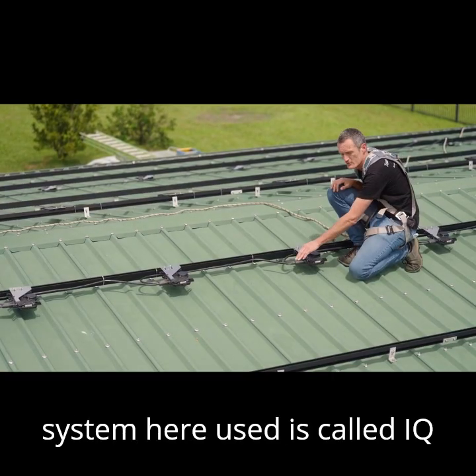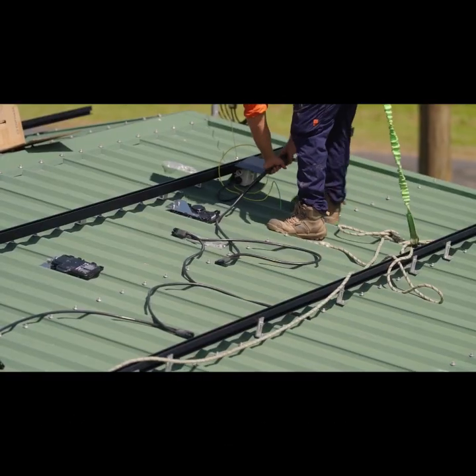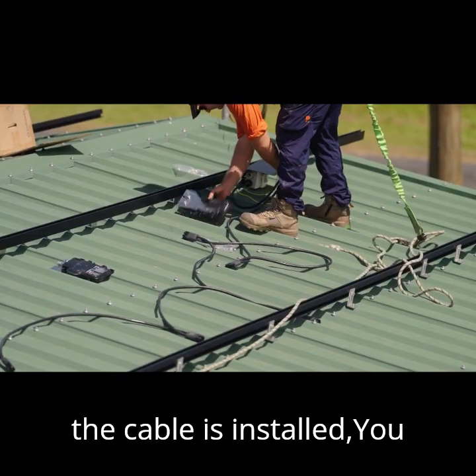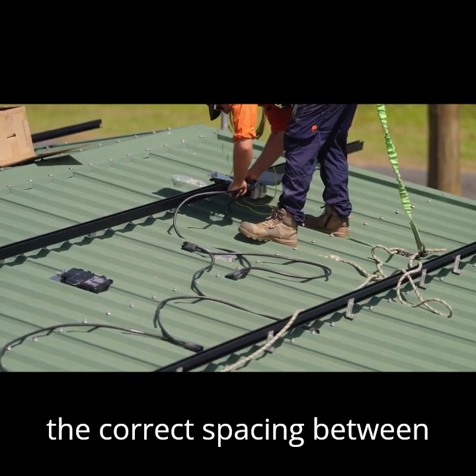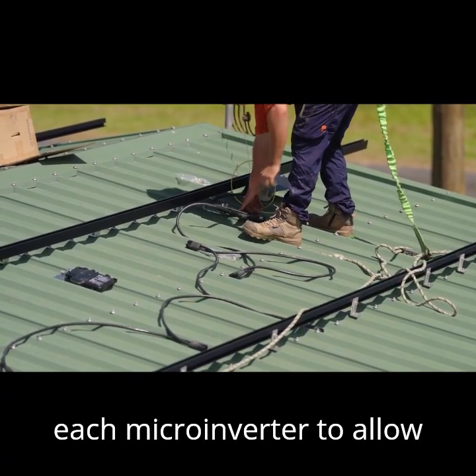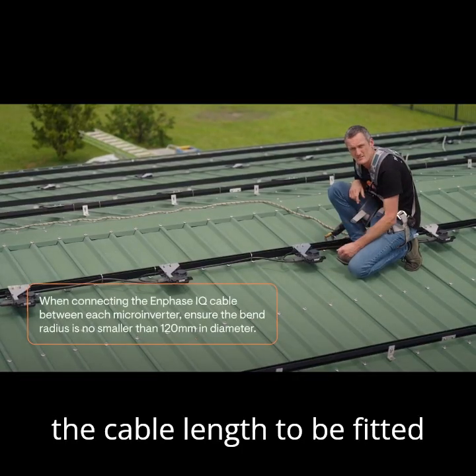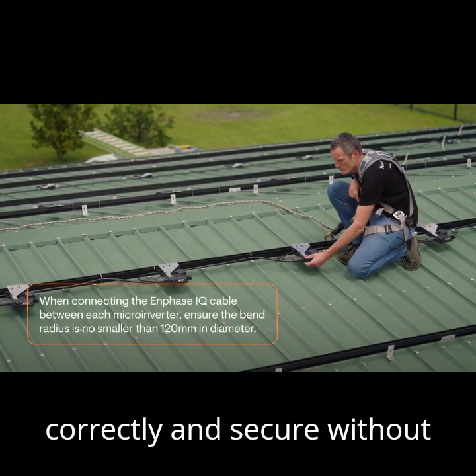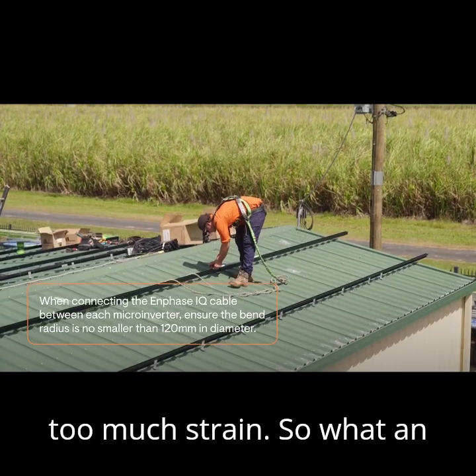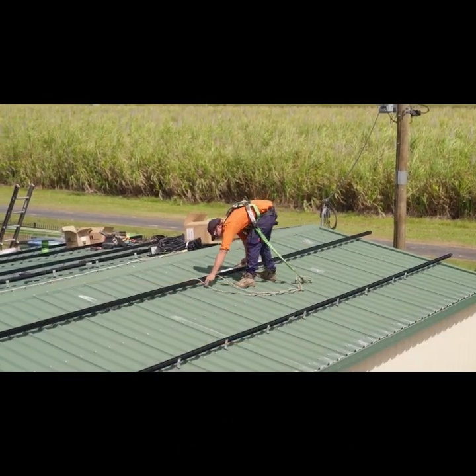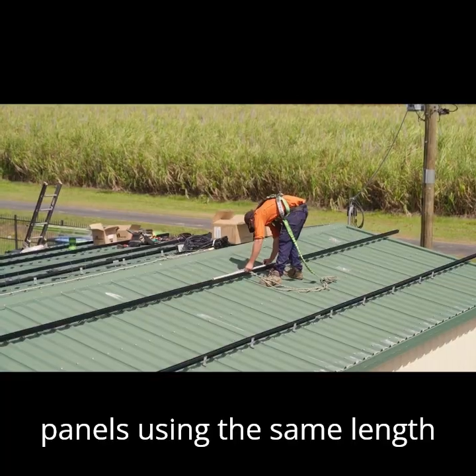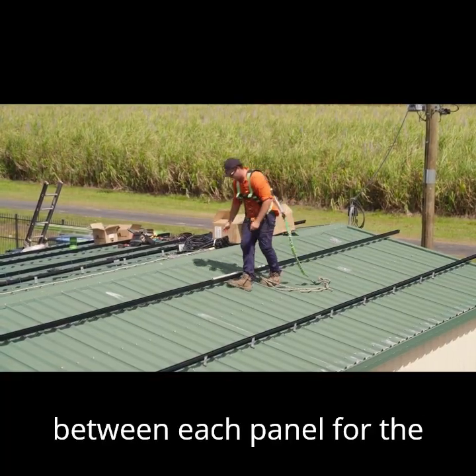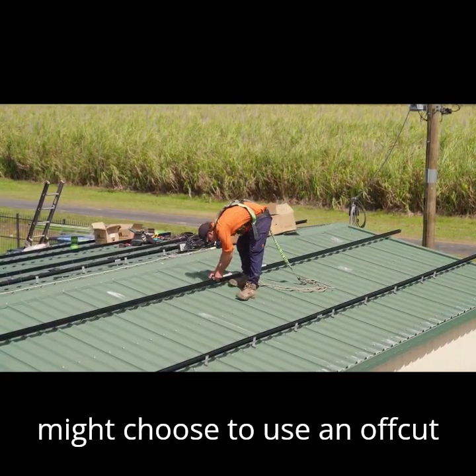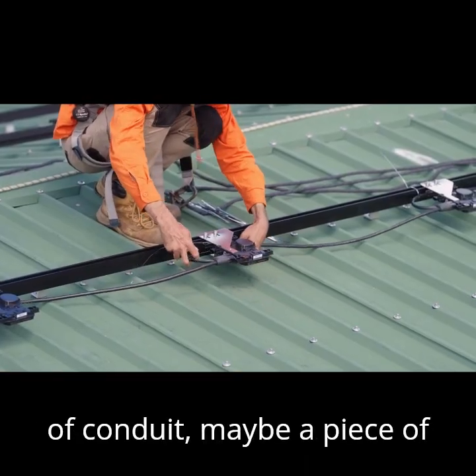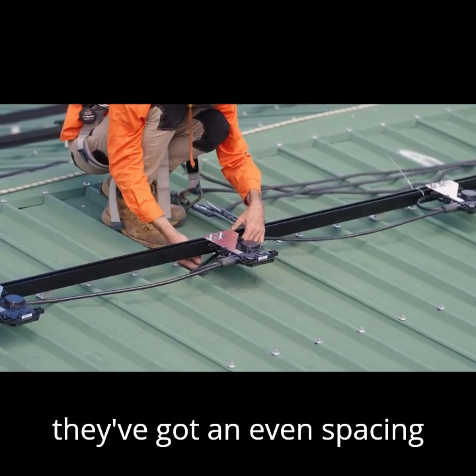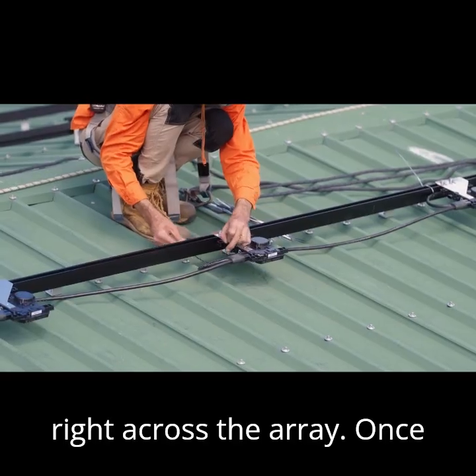The cable system used here is called IQ cable. When installing it, you want to ensure correct spacing between each microinverter so the cable length fits correctly and securely without too much strain. An installer will measure an even spacing under the panels, using the same length between each panel for the microinverter position, sometimes using an offcut of conduit or rail to the right length for even spacing across the array.